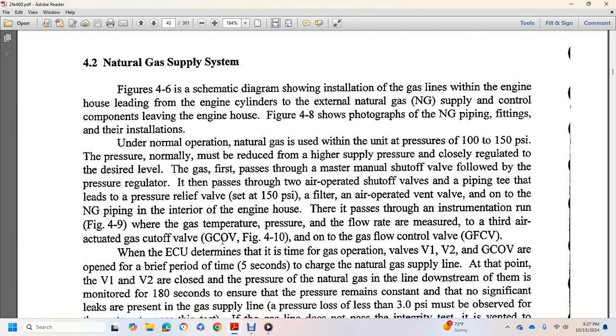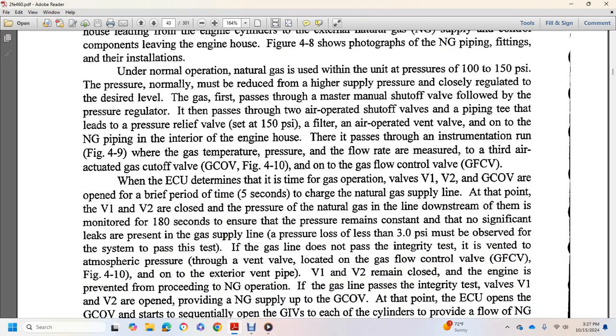These pass with the instrument running, figure 4.9, gas temperature, pressure, flow rate with a measure of the third air-actuated gas cutoff valve, the gas flow control valve. The engine control unit determines the time of the gas operation. Valve 1, valve 2, and gas control cutoff valve are open briefly with a period of 5 seconds with the natural gas supply with the deployment of the V1 and V2 closed with the pressure and natural gas in line downstream of them and monitoring at 180 seconds. Should the pressure remain constant and no significant leaks be present in the gas supply line, a pressure drop of less than 3 psi must be observed for the system to pass the test.